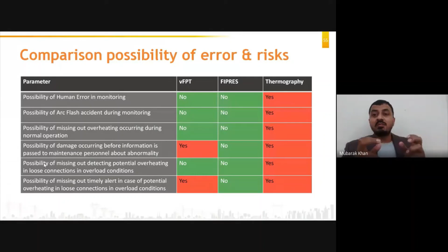Okay. Possibility of missing out detecting potential overheating in loose connection in overload conditions. It is possible in FIPRES and vFPT, not possible in thermography. Possibility of missing out timely alert in case of potential overheating in loose condition and overload conditions. So there is detecting and alert. Detecting is possible in both, but alert is possible only in FIPRES, not in thermography and vFPT. Okay. So that was about the comparison.